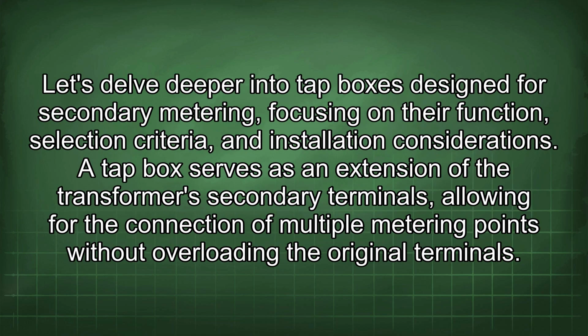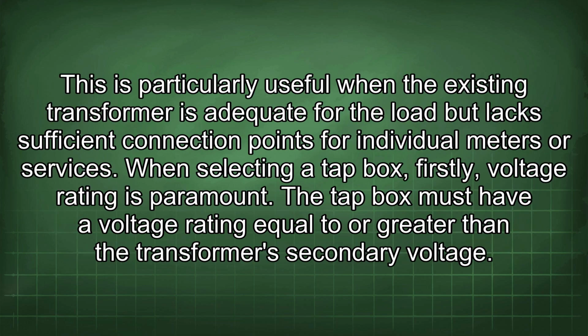Let's delve deeper into tap boxes designed for secondary metering, focusing on their function, selection criteria, and installation considerations. A tap box serves as an extension of the transformer's secondary terminals, allowing for the connection of multiple metering points without overloading the original terminals.